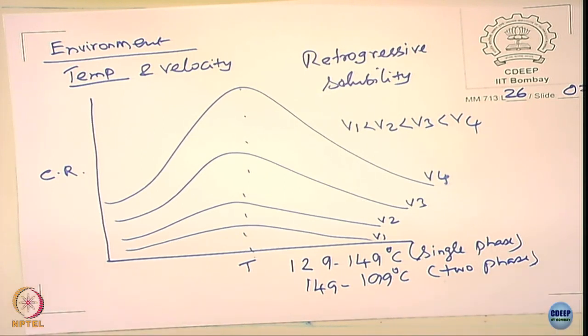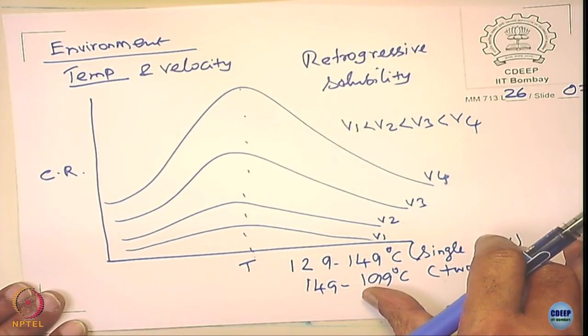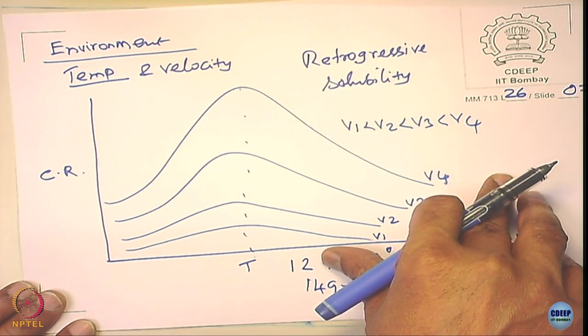So, what are the factors that then can control flow assisted corrosion? Velocity, the temperature, right, the pH. Now, all of them should be seen in the light of the ability to form an oxide film or to damage the oxide film. Please look at that. Okay. So, those factors which assist the formation of the film will lower the flow assisted corrosion, and those factors which dissolve the film will increase the flow assisted corrosion.